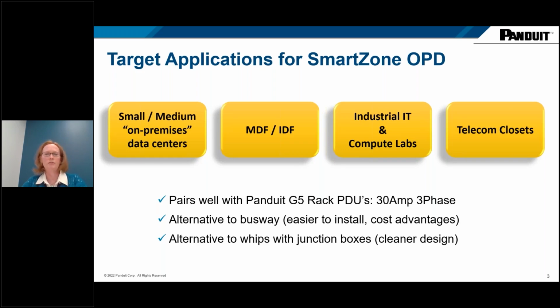This solution pairs very well with Panduit's Gen 5 rack PDUs, especially the 30 amp and 3-phase versions. It's a great alternative to busways—much easier to install, with a lot of cost advantages—and it's also a great alternative to the custom whips that an electrician would run. Oftentimes they're running junction boxes out above the cabinets and attaching those to, say, a ladder rack or a wire basket. This gives you a much cleaner design.